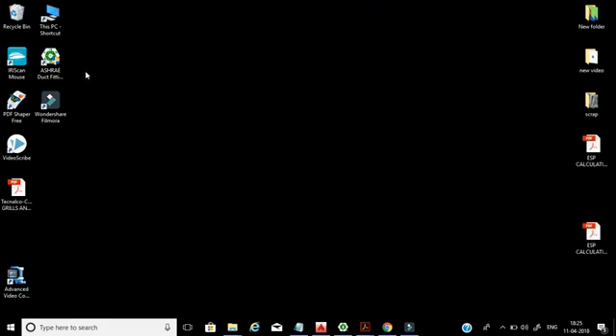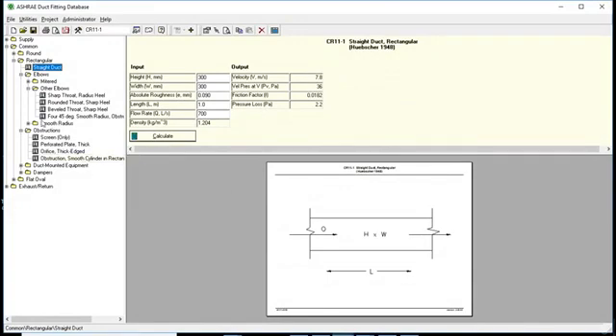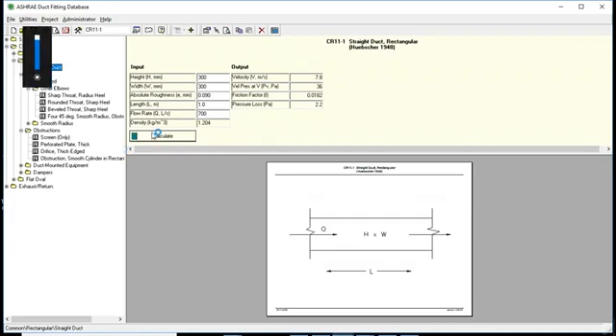To calculate using the ASHRAE Duct Fitting Database for ESP calculation, first of all we need this software. I will put a download link with this video. We need to open the ASHRAE Duct Fitting Database — I think it's already opened here from yesterday. It will be displayed like this. Here we need to put in some values, and we will get the pressure loss in Pascal.